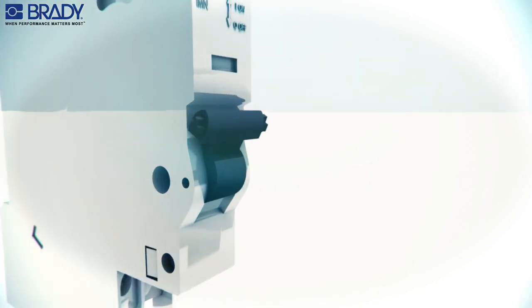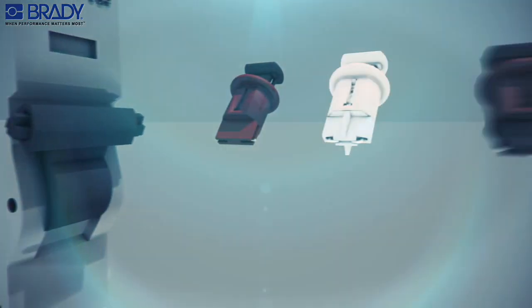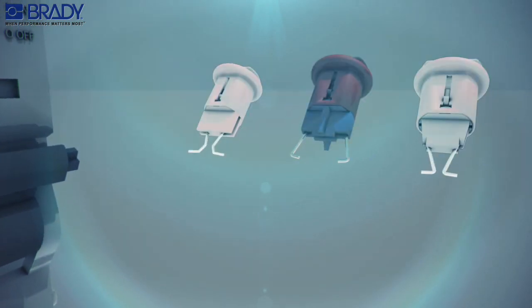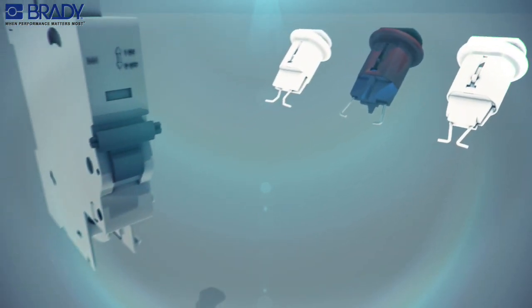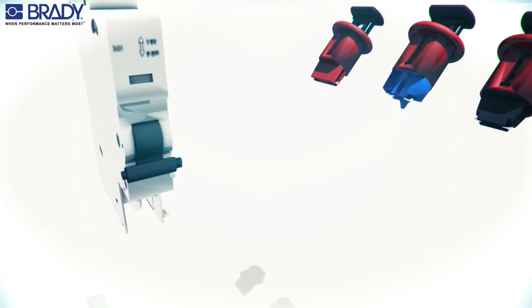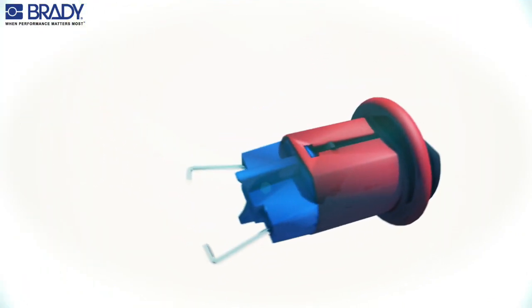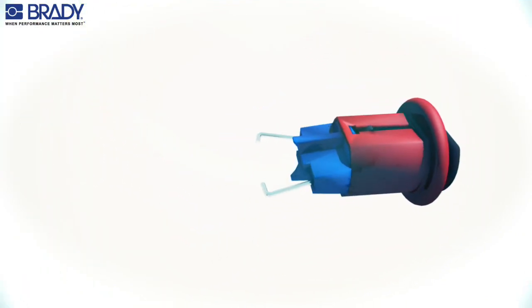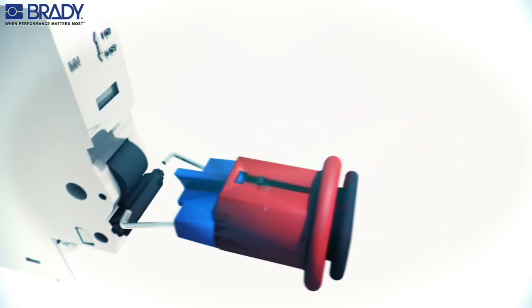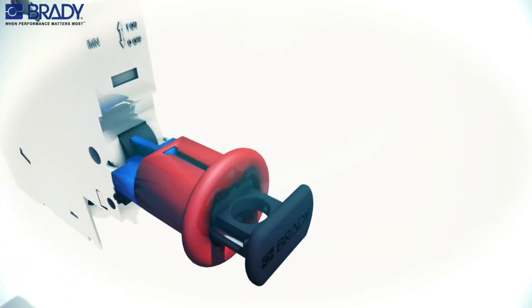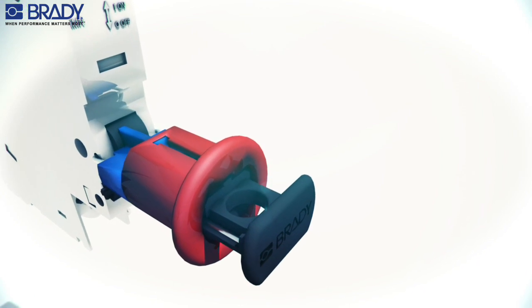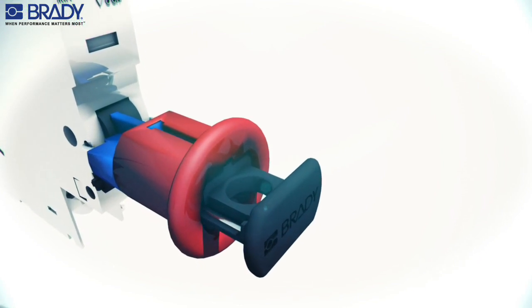Locate the small holes in the center of the circuit breaker casing and select the appropriate pin-in or pin-out circuit breaker device. Place the circuit breaker in the off position, press the lockout device push button to disengage the pins, then position the pins into the small holes of the casing by releasing the push button. Attach a Brady safety padlock.